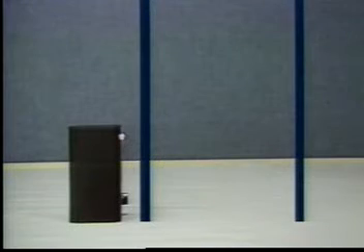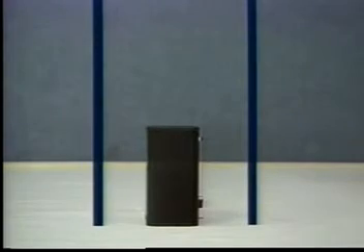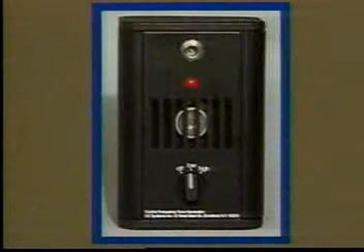And finally, it is important to know that the ultrasound signal does not pass through more than one medium effectively. Therefore, when testing an area with multiple surfaces, you may need to place the warble tone generator between the layers, such as between 2 walls. The warble tone generator can be an effective tool in difficult situations.